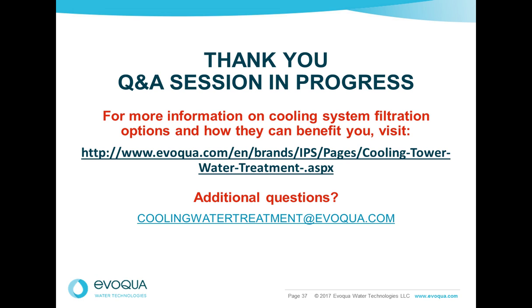Copper is normally a blowdown/wastewater issue, and there are specific ion exchange resins that will pick up copper specifically out of a blowdown stream. The one thing to note, though, if you've got copper, keep an eye on that, because you're going to want to know where that copper's coming from. If your copper's coming from your makeup water, that may not be a problem. Like the city of Chicago, where I'm at, there's a certain amount of copper in there just in the piping. But if the copper in your tower is exceeding what your makeup water is providing, now you've got a corrosion issue. So it's an indicator.